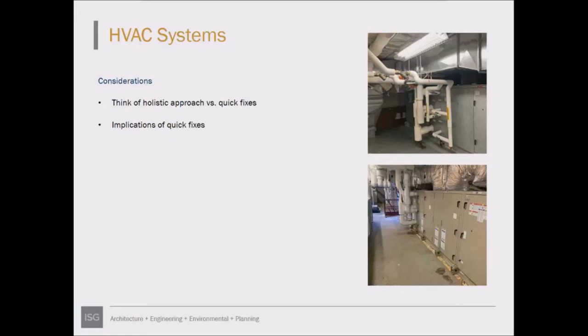Here are some HVAC quick fixes. Bottom left, in the middle of winter when it was freezing cold, they couldn't get the univent to work, so they took off the grill, put in a piece of plywood, and it's been there for years - meaning no fresh air going into the classroom at all. Bottom right is a coil that had a leak in it, so they cut it off and patched it. Who knows the last time heat or chilled water went through those coils - since it was an interior room, they weren't too concerned.